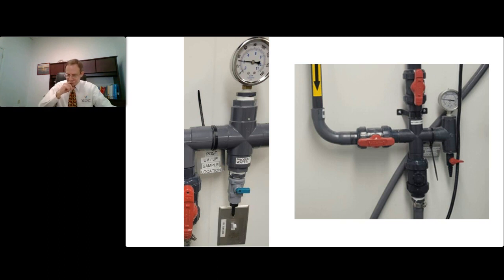So anyways, the other thing too about these sampling ports: they're not zero dead leg valves, so they allow a fair amount of water to sit around in crevices around the sampling port spigot. In essence, biofilms were being allowed to form where they were testing the water. And with water being drawn only once a month, this led to slow progression of biofilm growth with each ensuing month. And the drops from the critical water recirculation loop to the equipment was also significant.